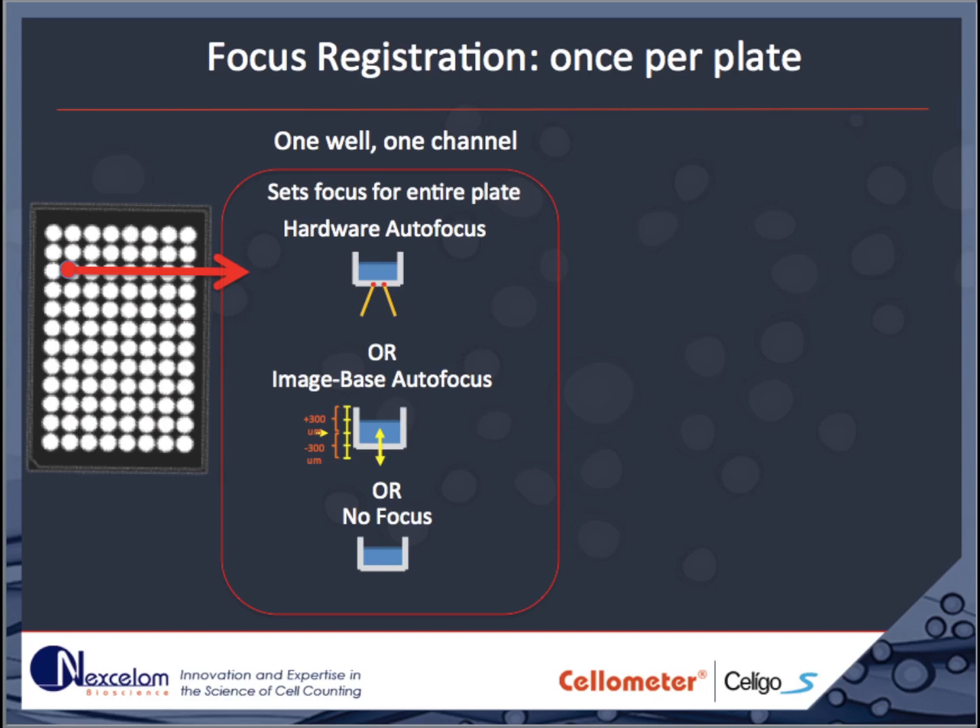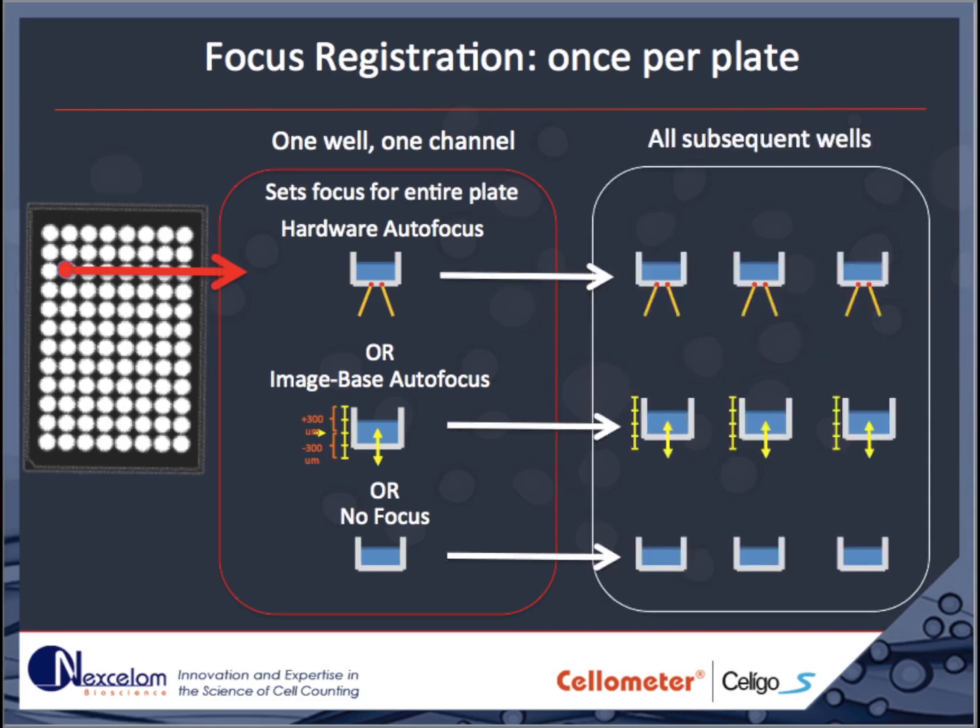Each time a plate is imaged on the Celigo, the focus must be registered. This occurs in one well, in one channel only, for each plate. Focus registration defines the focus parameters for the entire plate. At the time of focus registration, the user chooses to use either hardware or image-based autofocus for the entire plate. It is also possible to choose no focus, in which case the entire plate will be imaged without adjusting the focus. This can be useful when imaging large objects of greatly varying size.